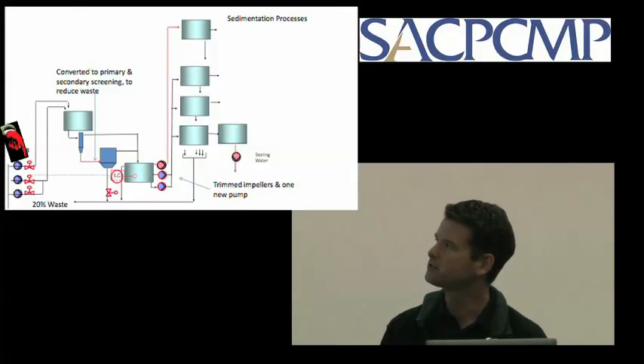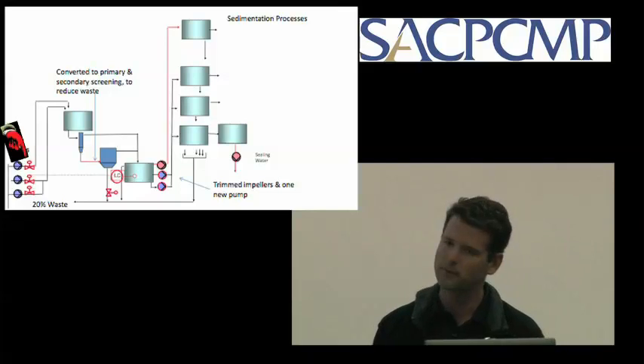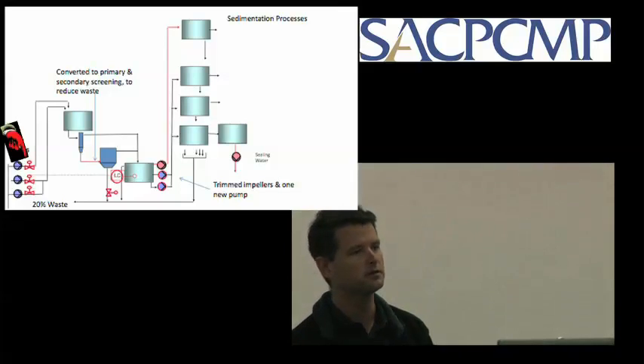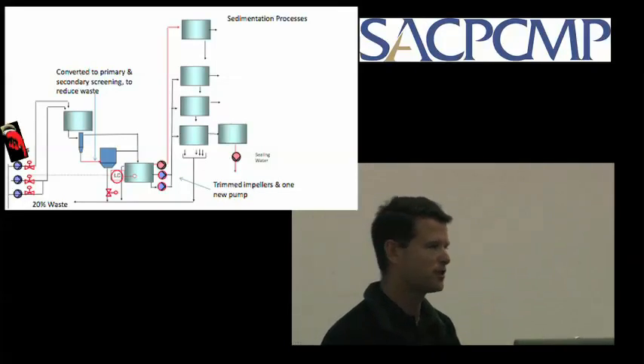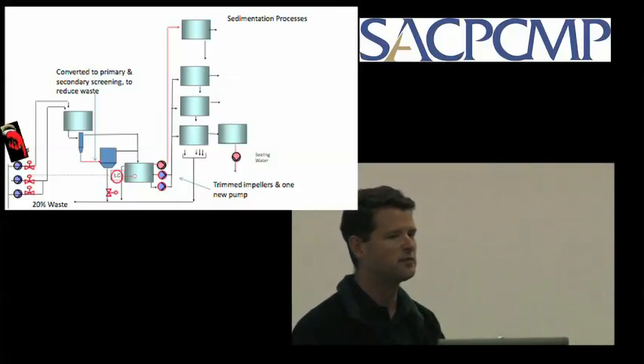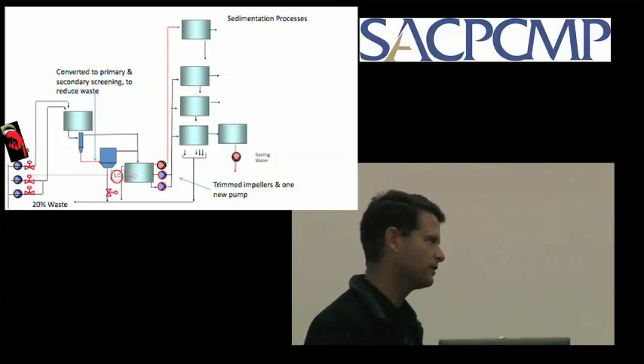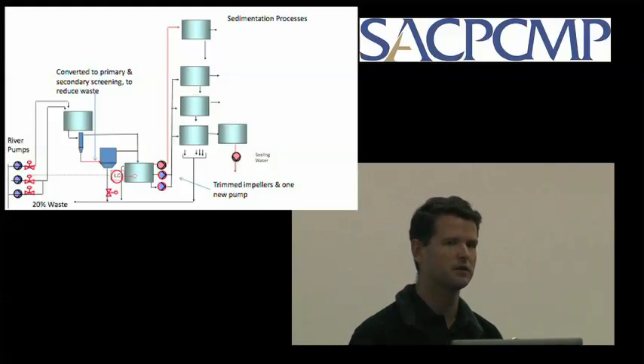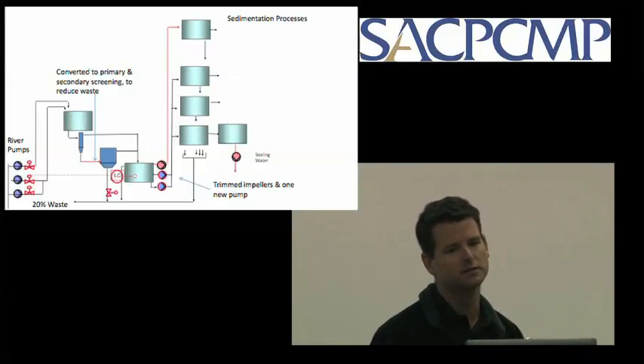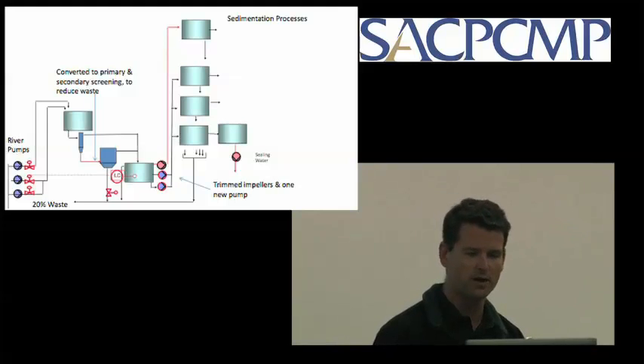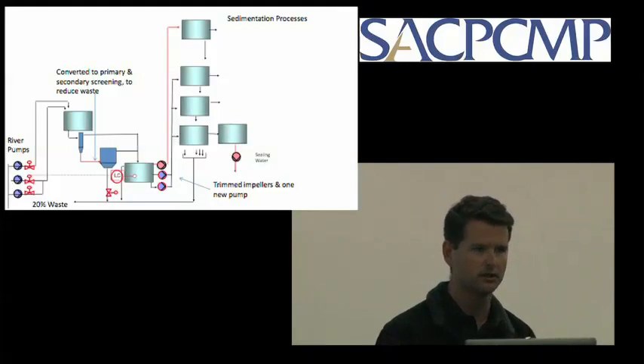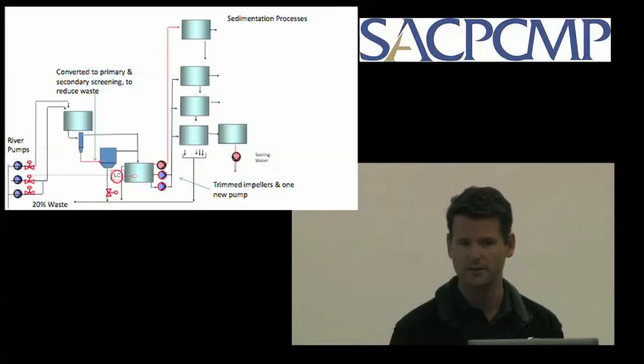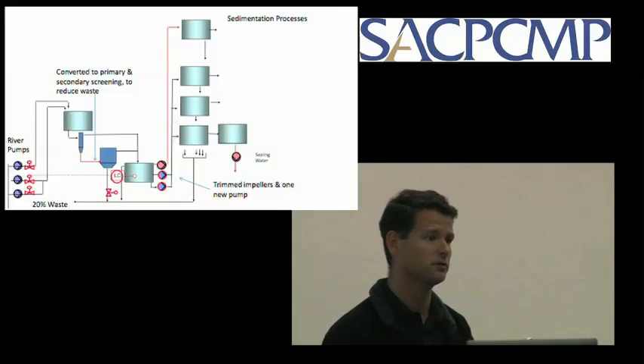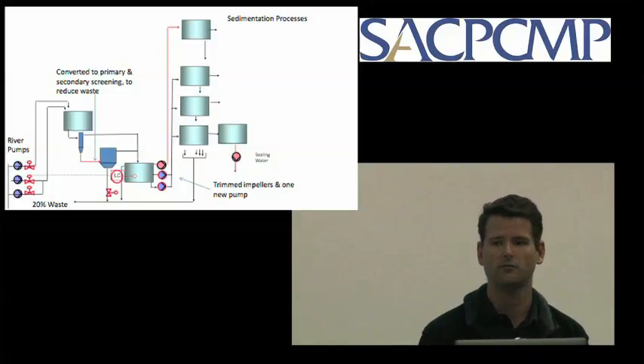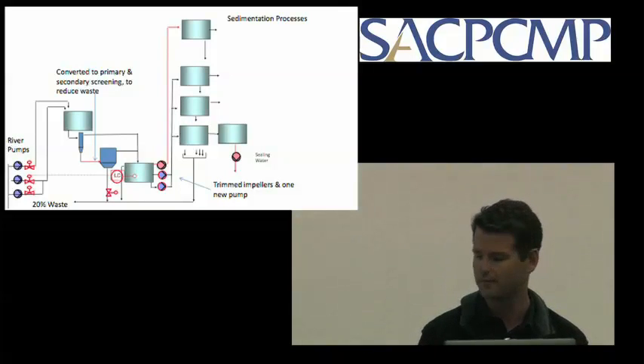That had two reasons. These pumps are drawing up from the river, so when you stop this whole plant, you've obviously lost your prime on those pumps. So now you have to reprime them, and it was a very manual process before. They had little Nash vacuum pumps priming the pumps, so we came up with a whole automated system of detecting when they're primed, with on-off valves so that you can prime each pump individually. So that was another whole complication to switching this plant off. They very rarely previously had to go and prime them because they were just running all the time.